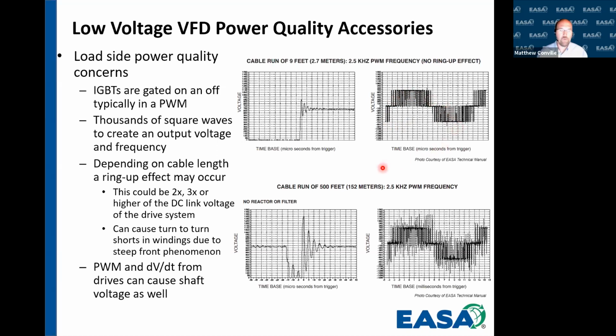As our cable gets longer, we can get what we call a ringing up effect. With this ringing up effect, we could have peak voltages that are 2 to 3 times the DC link voltage of the drive system. And this can cause turn-to-turn shorts in our windings due to a steep front phenomenon, or DVDT, and peak voltage. So the main thing we've got to be careful about is not only that peak voltage, which is somewhat like what you would expect to see with our surge testers, but also the rate of rise, which is DVDT.